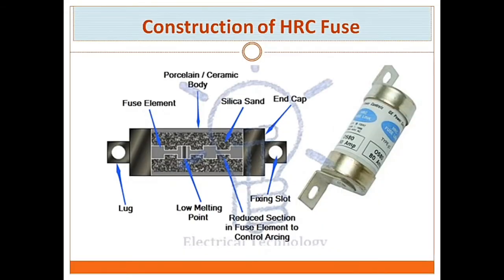Construction of HRC fuse. It consists of a heat resisting ceramic body and having metal end caps to which is welded silver current carrying element. The space within the body surrounding the element is completely packed with the filling powder. The filling material can be chalk, plaster of Paris, quartz or marble dust, and it acts as an arc quenching and cooling medium so that it carries the normal current without overheating.